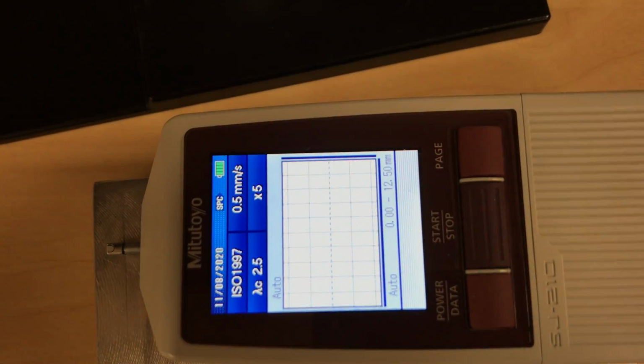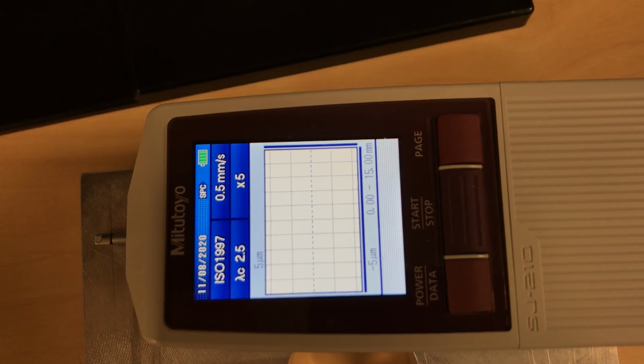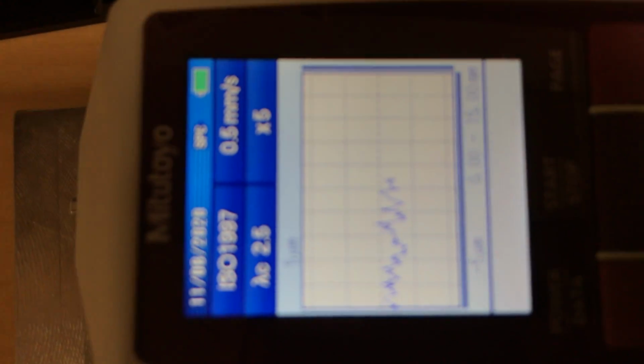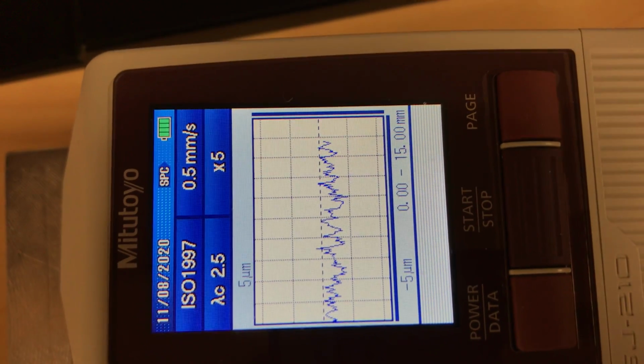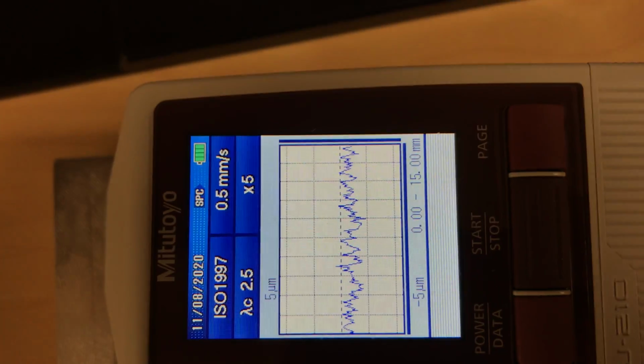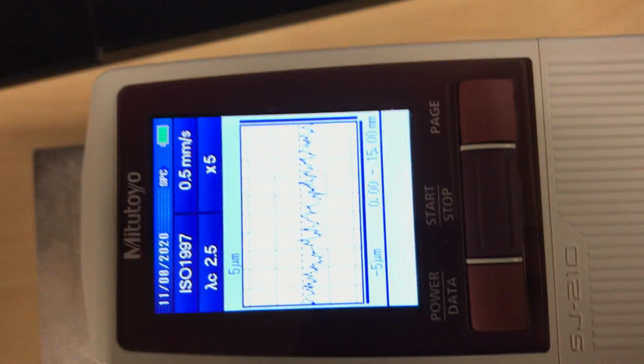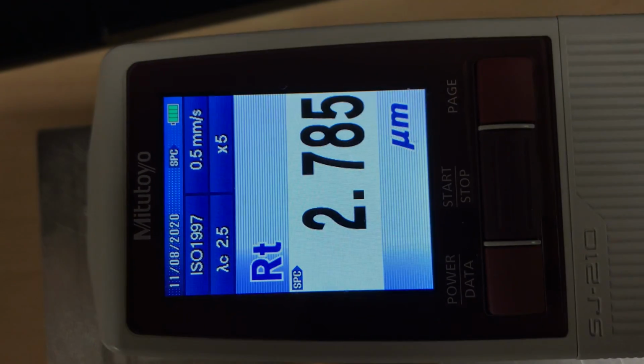We just press on this button, and the probe is going to move to the inside, as you can see here. It's moving actually, but it's too slow. And when it finishes, you can see that it's sketching the flows, the tops and the bottom, until it reaches the end of the movement, and then it's going to stop and make the calculation. Actually we have the Gauss filter programmed in this software, and it's going to do the calculation and give you the approximate height. So the height of this stuff is going to be 2.785 micrometers, as you can see here in the unit.